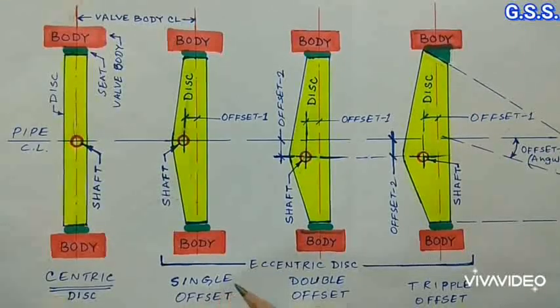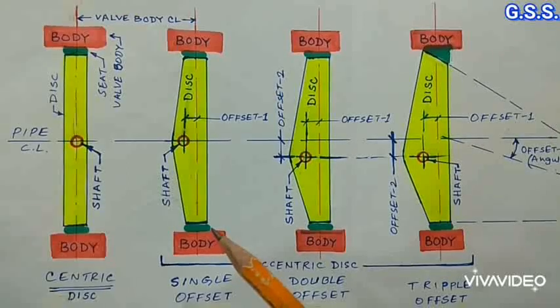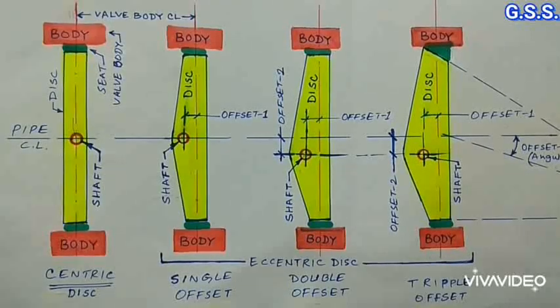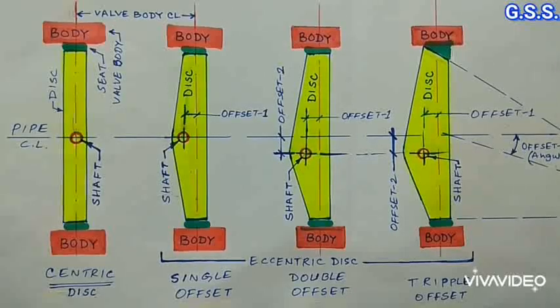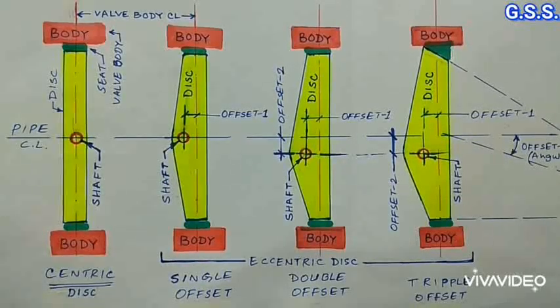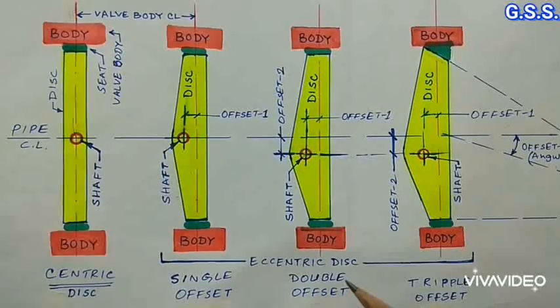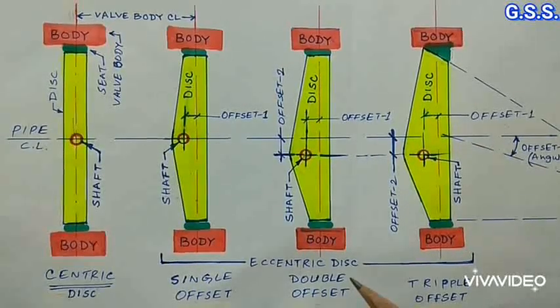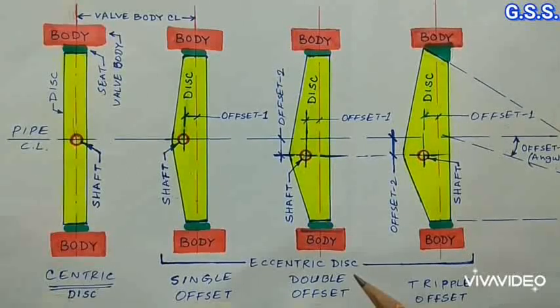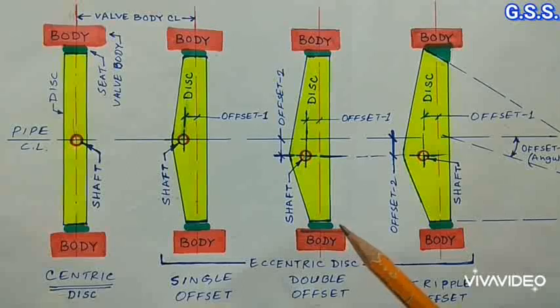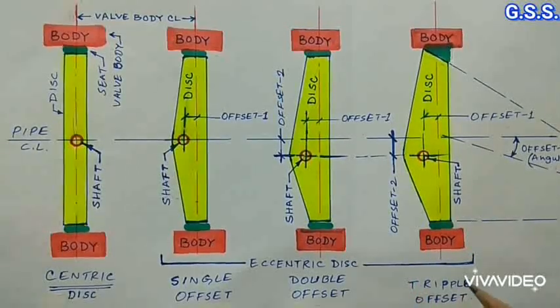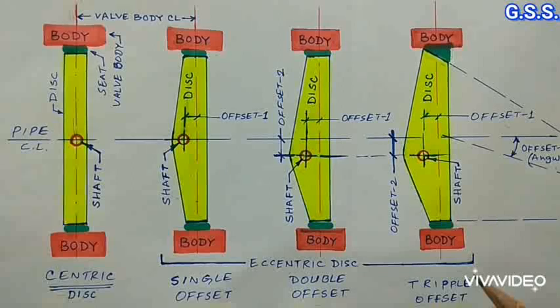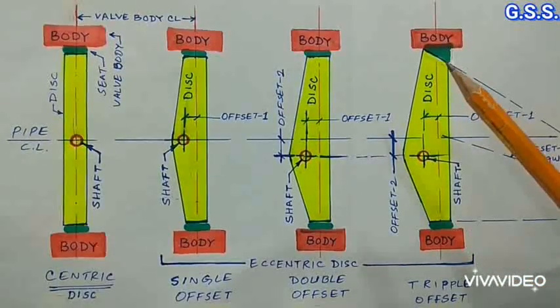Centric and single offset valves are having soft EPDM or nitrile seat and used for non-critical service up to 10 to 12 bar pressure and 80 degree Celsius temperature. That means up to 150 pound class only. Double offset valves are used for high pressure application up to 70 bar pressure. That means up to 600 pound class. And temperature up to 200 degree Celsius if VITON or PTFE seat is used. Triple offset butterfly valves can be used at much higher pressure and much higher temperature since there is only metallic seat. That means metal to metal contact.